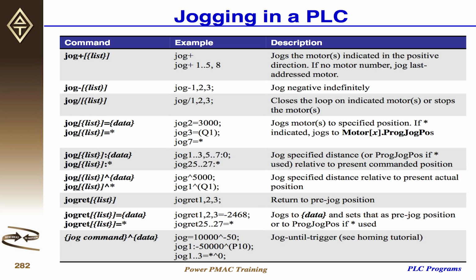You can also jog incrementally from present commanded position with the jog : command, or incrementally relative to the present actual position with the jog ^ command. You can return to the pre-jog position with jog ret.